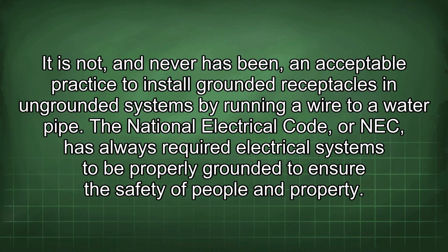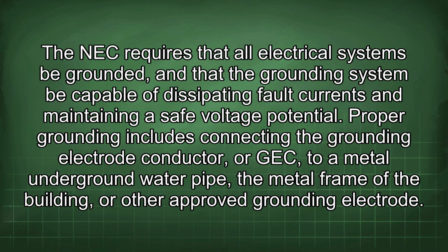It is not, and never has been, an acceptable practice to install grounded receptacles in ungrounded systems by running a wire to a water pipe. The National Electrical Code, or NEC, has always required electrical systems to be properly grounded to ensure the safety of people and property. The NEC requires that all electrical systems be grounded and that the grounding system be capable of dissipating fault currents and maintaining a safe voltage potential.